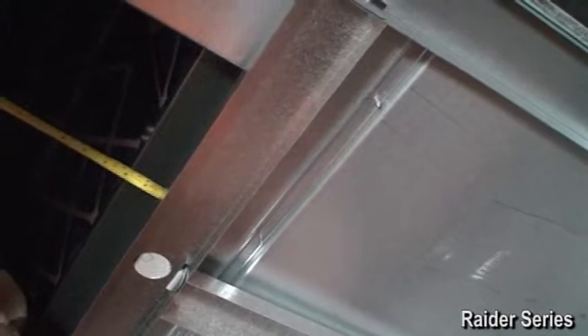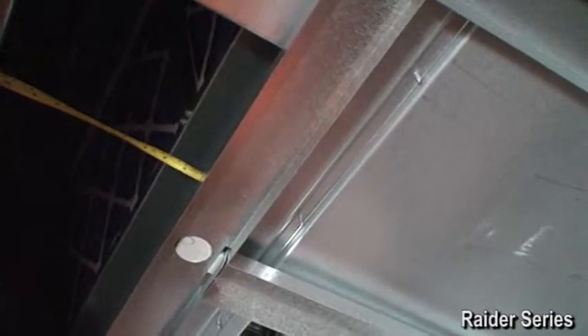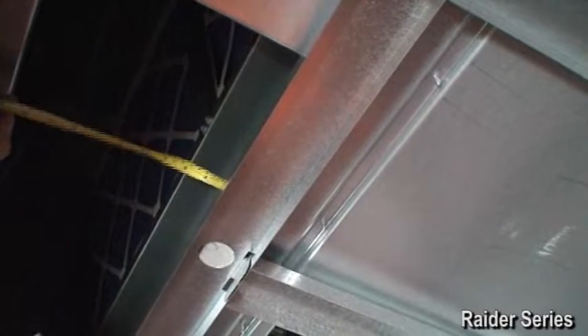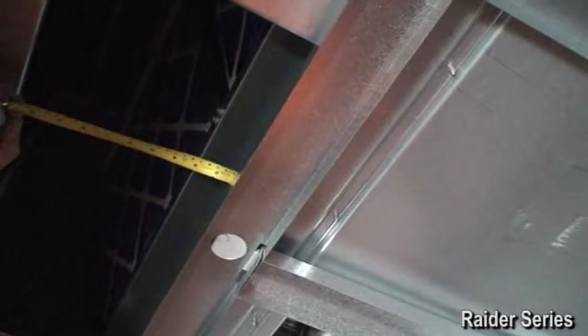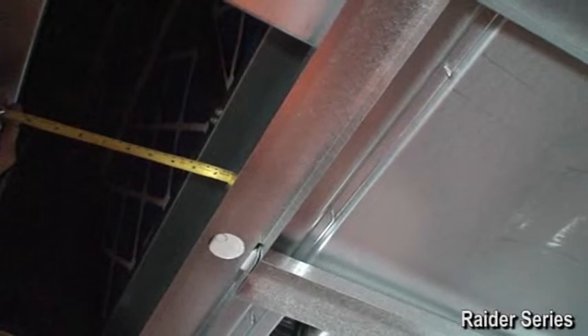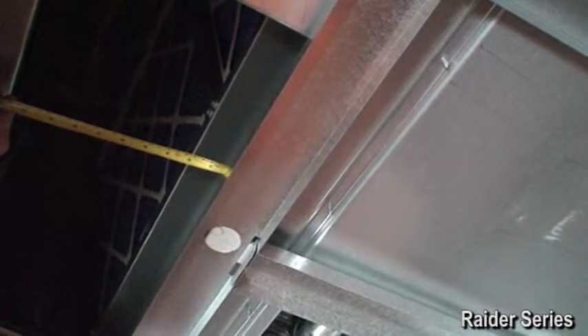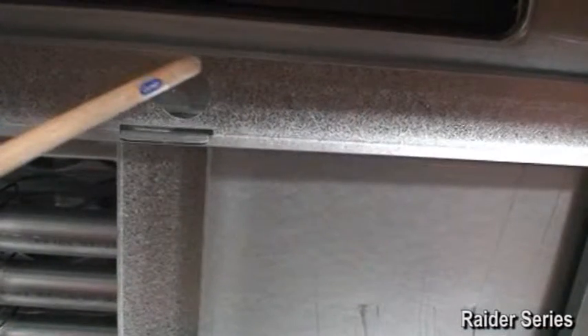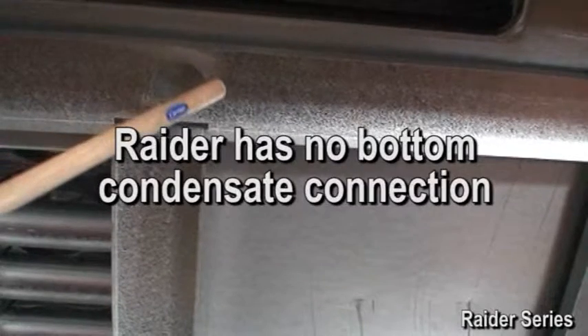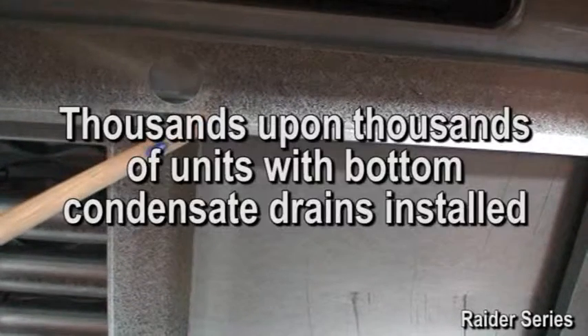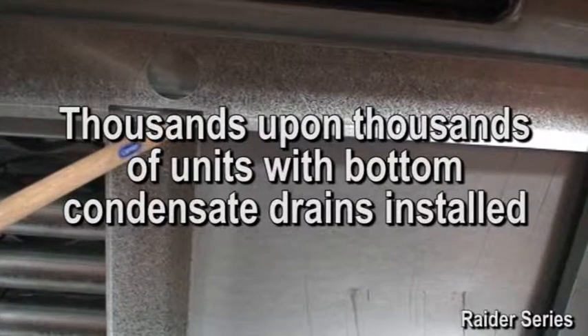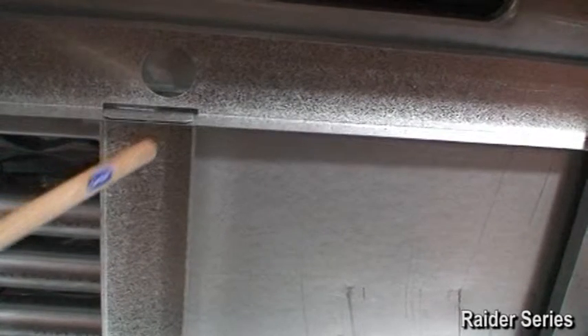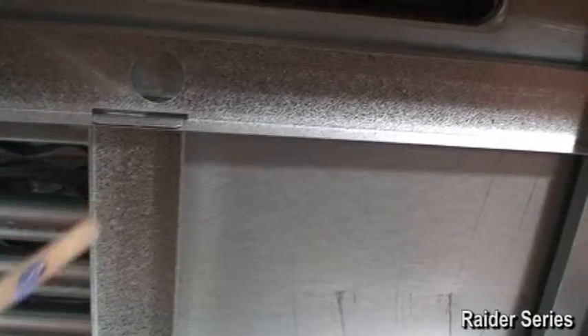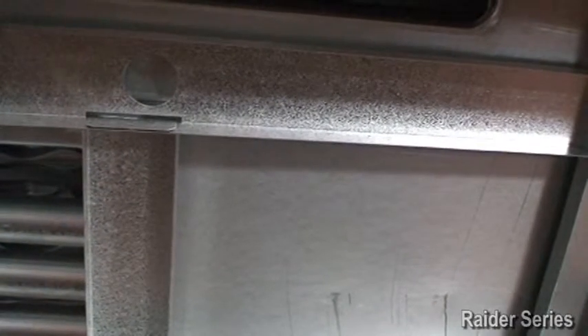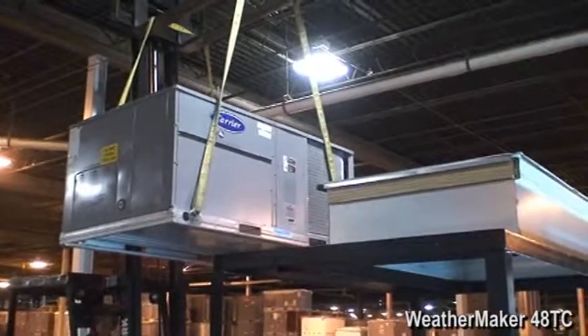Upon further review of this critical finding, it was clearly due to the fact that the unit is larger than Carrier's and had a lot of area to move around on the curb. This was seen as a critical issue and caution needs to be taken if using other than a Carrier direct replacement model. Oh, one last thing. The competitor's model did not have a bottom condensate drain connection on the unit. Seeing that Carrier has thousands upon thousands of units installed with bottom condensate drains due to code or waste management restrictions, there is a good chance you will find this feature is missing once the unit is installed and the crane has left. Now let's look at the Carrier unit.